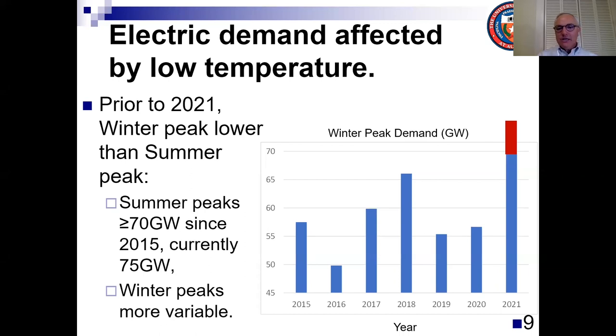The only exception is that blue bar for this year. The top of that blue bar is at 69 gigawatts, which is in fact the peak demand that was served in ERCOT in February. Very soon after that peak demand was served, we had several generator outages and curtailment, and I will describe that in more detail later. But what then happened was that not all the demand could be served. There were estimates of what the peak demand would have been had it been able to be served, and those peak estimates are about 75 gigawatts.